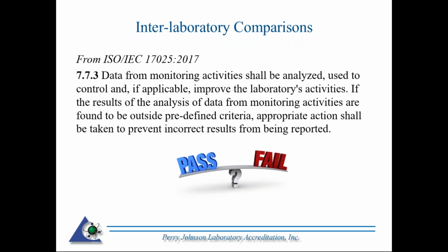I put this in here - 773, it's required. We've written non-conformances on this in more than one case. Let's say bare bones minimum, you're doing yourself and another organization for an interlab test - you either compare or you don't compare. You have to analyze the data, so you need some sort of vehicle for determining whether or not the results are in agreement, and we need to see a record of that analysis. That's the requirement from 773. What I've seen is: here's our results, and here's their results - okay, I see the results, but did they pass, did they fail, are they in agreement, and what are you basing that on?